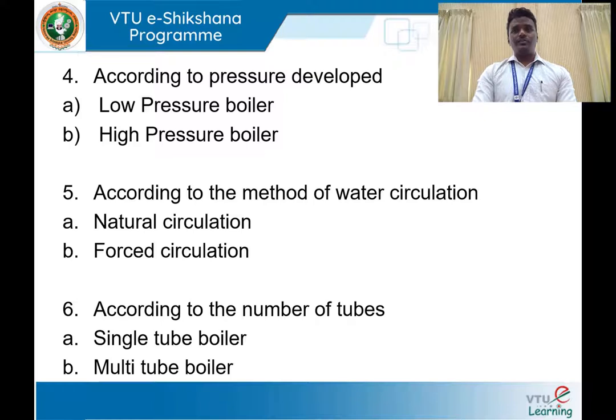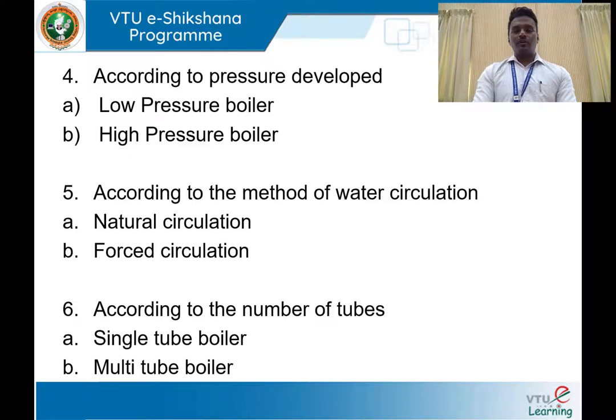Depending on the method of water circulation — water is the raw material for steam generation, pumped into the boiler shell. Once heated, the heated water molecules move upward, creating a convective current. If no pump is used to circulate water inside the boiler shell, it is known as a natural circulation type boiler. If a pump is used for circulating water, it is a forced circulation boiler.